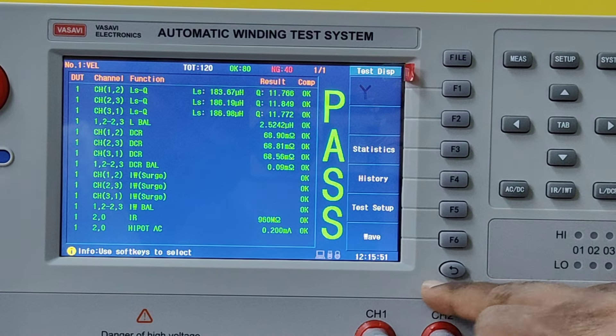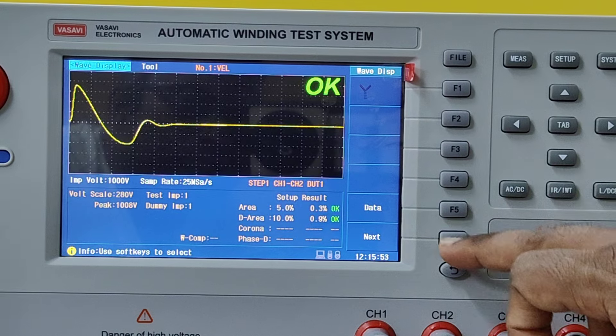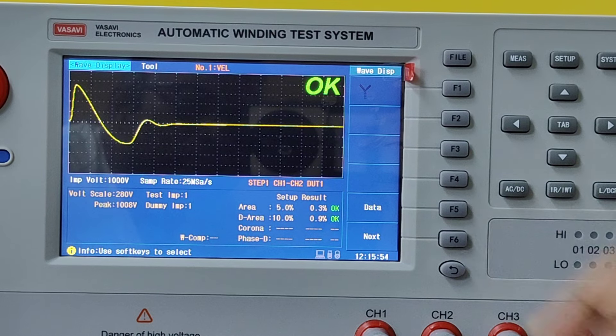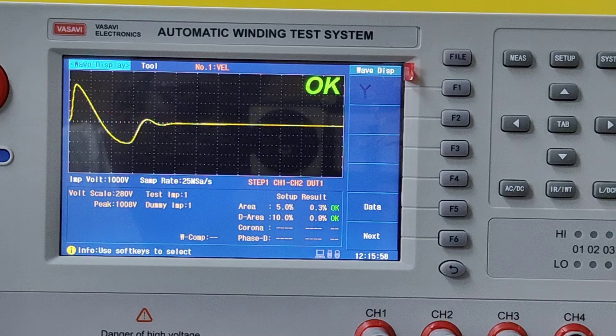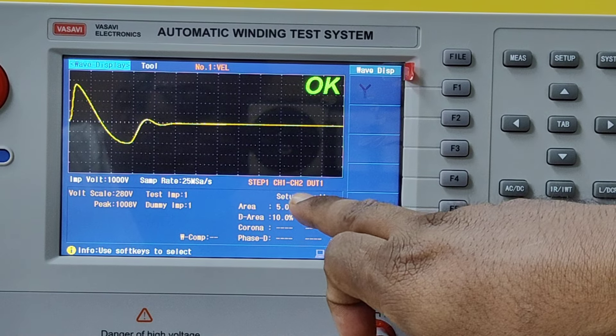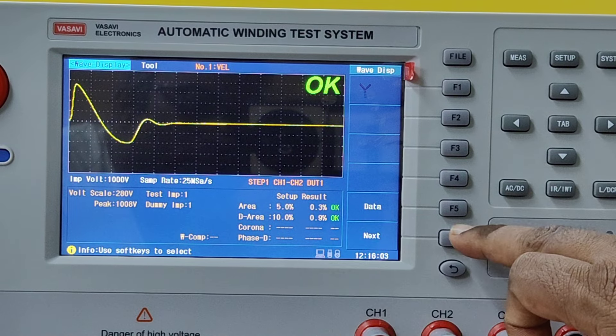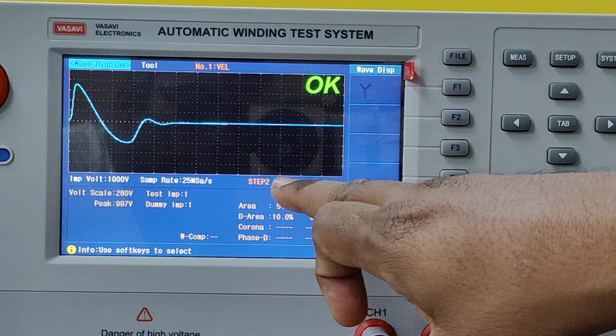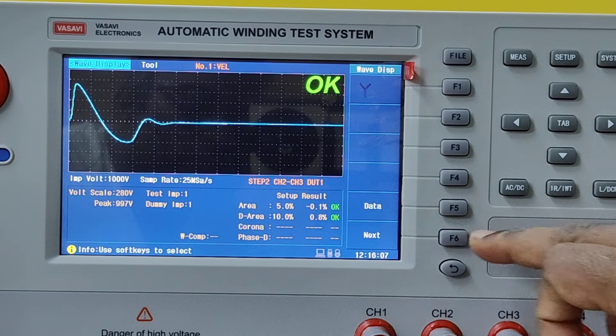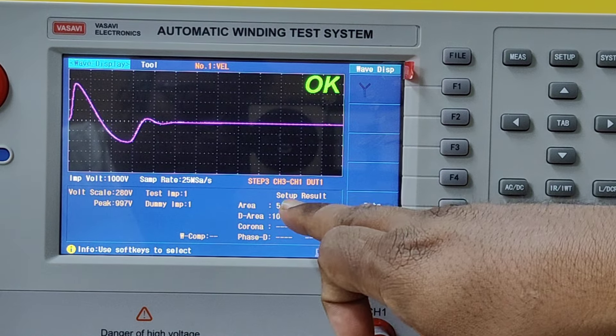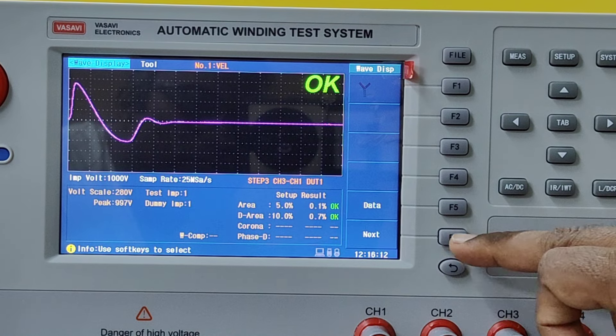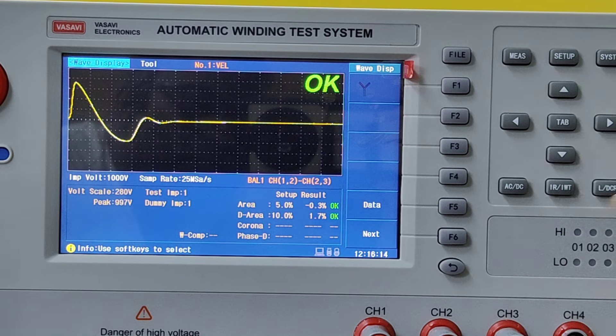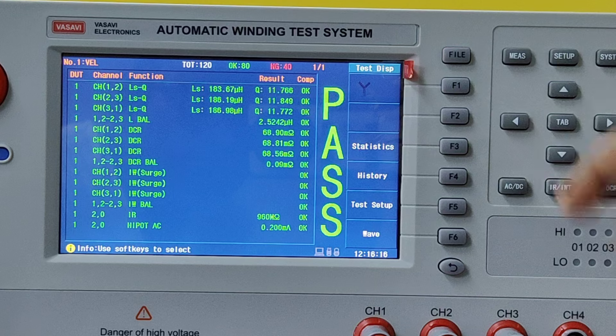You can also see the waveforms. This is the waveform of the first phase, that is channels 1 and 2. You can see channel 1 and channel 2. If you want to go for the second phase, that is channel 2 and channel 3. And channel 3 and channel 1 for the third phase.